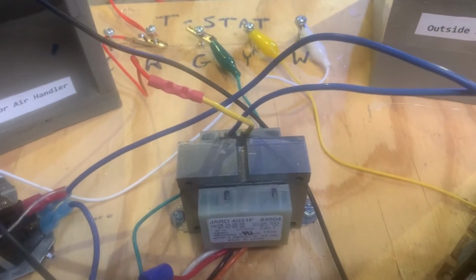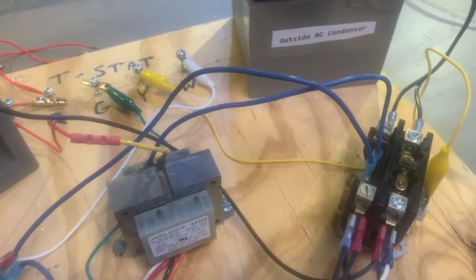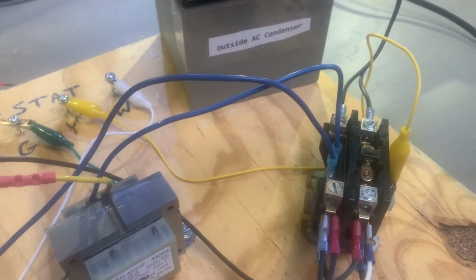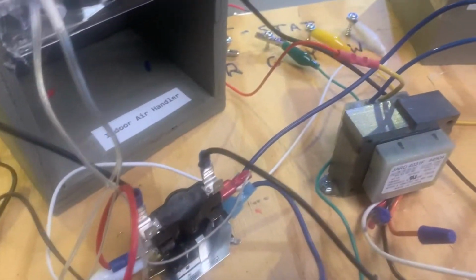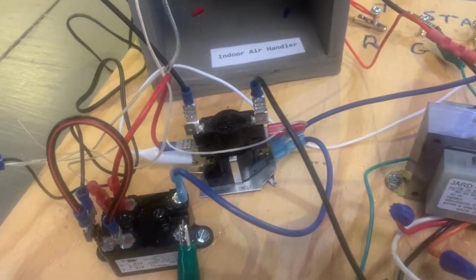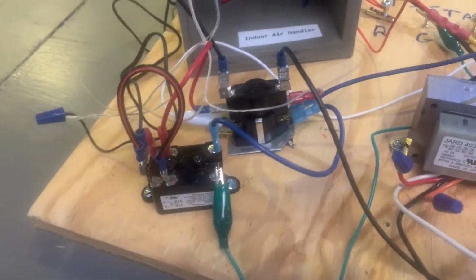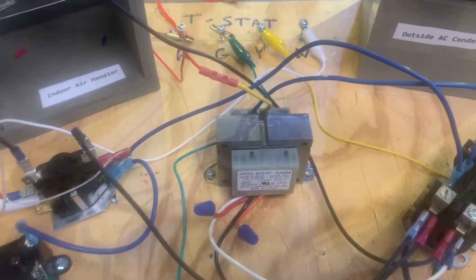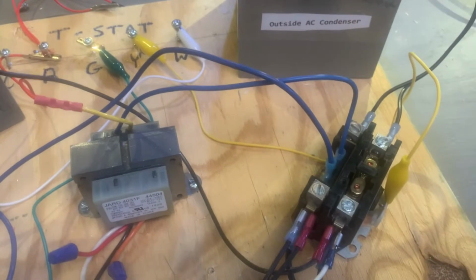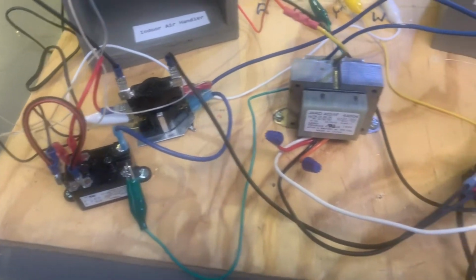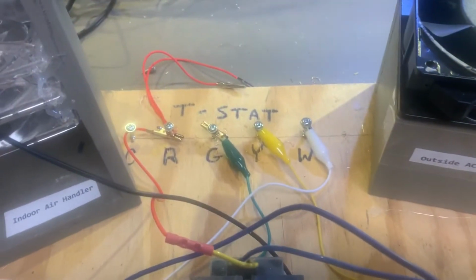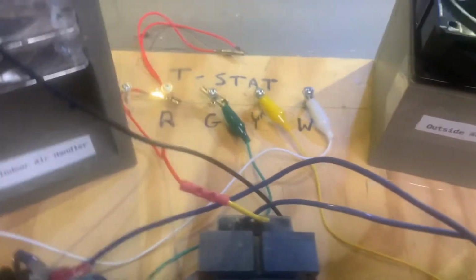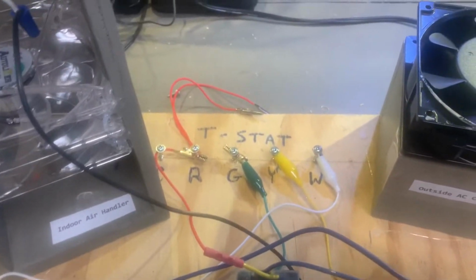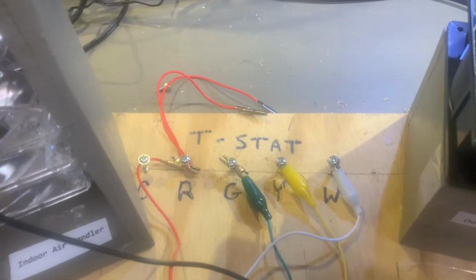The blue, which is the other half of our 24 volts, I just have it jumpered. It's my common, and it's jumpered from relay to relay. You can see it goes over here to the contactor first, and then it comes over to the sequencer, and then I've got a jumper from the sequencer coil over to the fan relay coil. So we have our 24 volt common blue coming out of the transformer and then jumpered to one side of the coil on each one of our relays. The opposite side of the coil on each relay has a jumper that goes back to the thermostat. So since our red is connected to the other half of the 24 volts that comes out of the transformer, this is where we make our final connection.